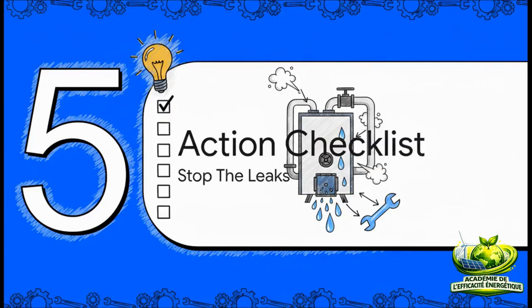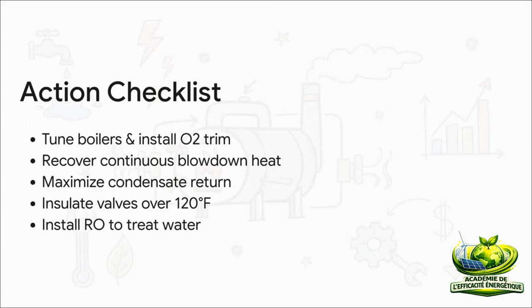Okay, we've covered a lot of ground. Let's move to our 5-point action checklist. Consider this your roadmap for slashing those utility bills and cutting emissions, all without having to buy a brand new boiler. Number 1, tune your boilers and get an O2 trim system installed to lock in that perfect excess air ratio. Number 2, get a heat exchanger in there to recover the thermal energy from your continuous blowdown.